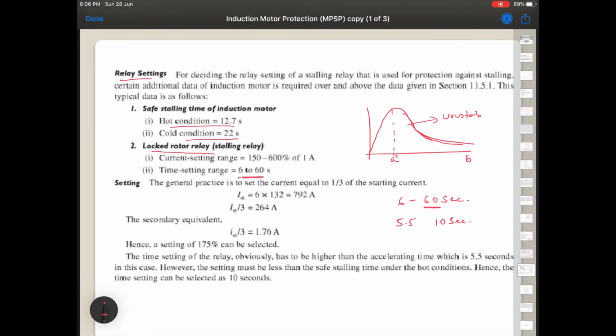So as explained, it is somewhere between 6 to 60 seconds, and the current here we are taking is 150% to 600%, that is 1.5 times to 6 times the rated current, which is 1 ampere. So here the thumb rule, in general practice, is to set the current equal to 1/3 of the starting current. The starting current is 792, so 1/3 of which is 264. If you convert this to secondary by dividing 264 by 150 ampere, we will get 1.76, which is almost 175%, which is well within this range.